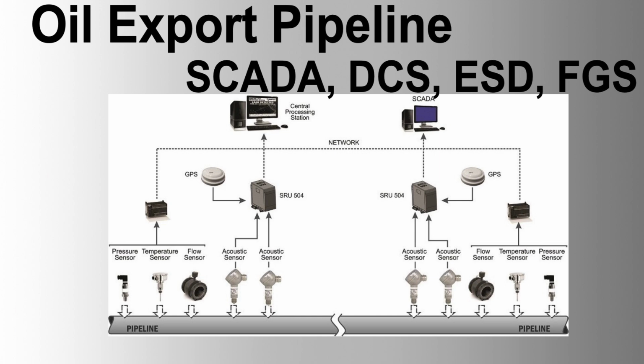Alarm handling, immediate activation of audio-visual alarms, shutdown commands, and fire suppression systems. Integration, interfaces with ESD and SCADA systems for coordinated emergency response. Maintenance bypass functionality with authorization and logging features. Redundancy, redundant control panels, power supplies, and communication networks to ensure reliability.